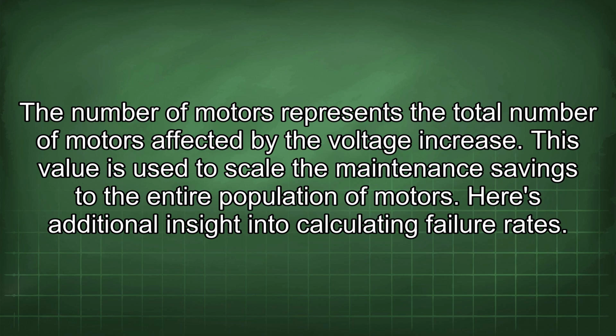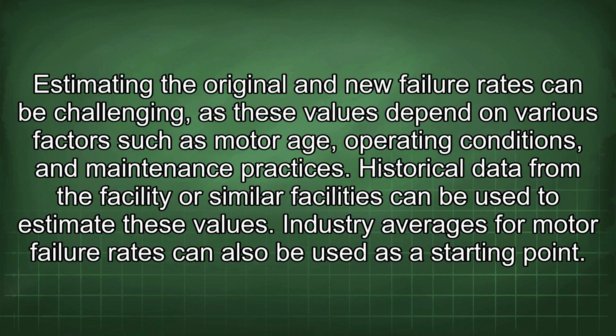Here's additional insight into calculating failure rates. Estimating the original and new failure rates can be challenging, as these values depend on various factors such as motor age, operating conditions, and maintenance practices. Historical data from the facility or similar facilities can be used to estimate these values. Industry averages for motor failure rates can also be used as a starting point.